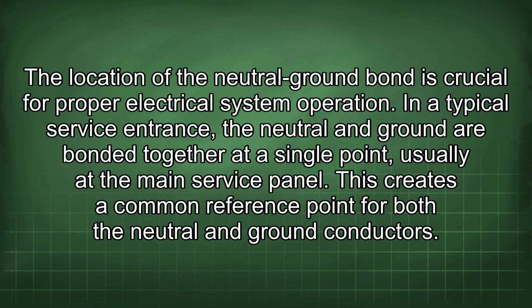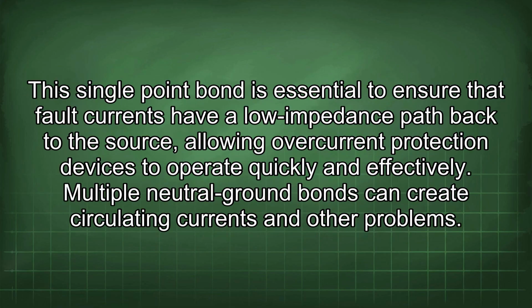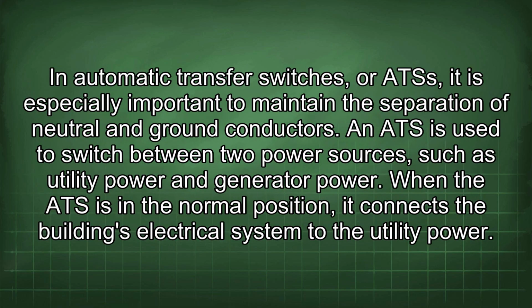The location of the neutral ground bond is crucial for proper electrical system operation. In a typical service entrance, the neutral and ground are bonded together at a single point, usually at the main service panel. This creates a common reference point for both the neutral and ground conductors. This single point bond is essential to ensure that fault currents have a low impedance path back to the source, allowing overcurrent protection devices to operate quickly and effectively. Multiple neutral ground bonds can create circulating currents and other problems. In automatic transfer switches, or ATSs, it is especially important to maintain the separation of neutral and ground conductors.